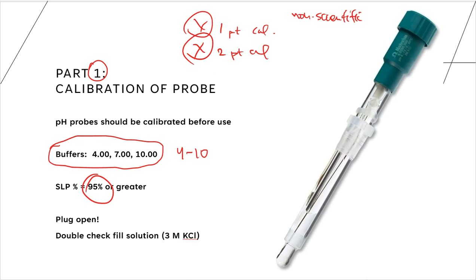If my value is lower than 95, then that means that this probe is not ideal. I probably need to recalibrate. I probably need to first, if I was going to do anything, just put fresh buffer on the probe and do the recalibration again and see what I get.